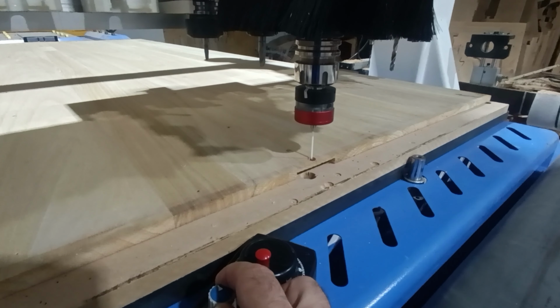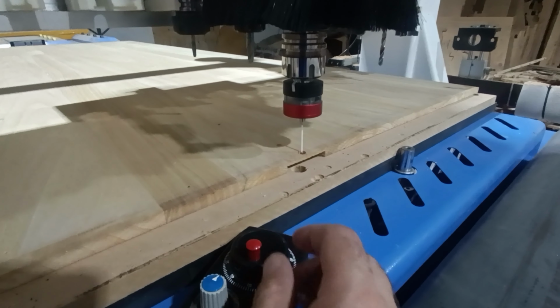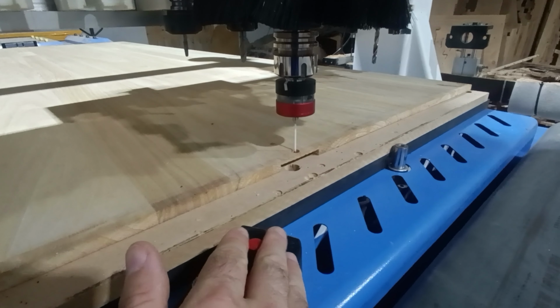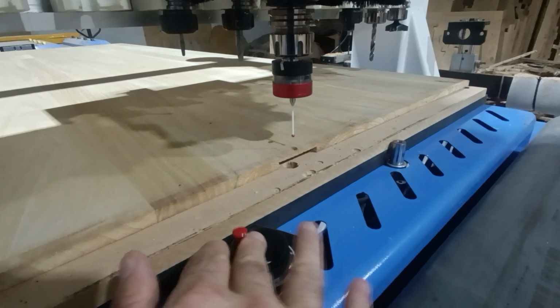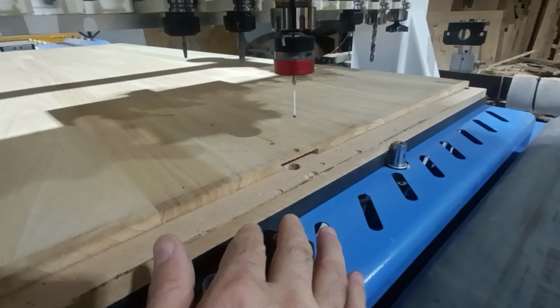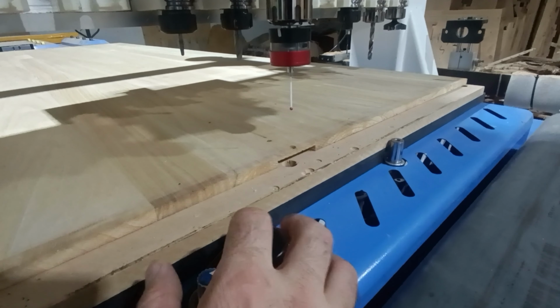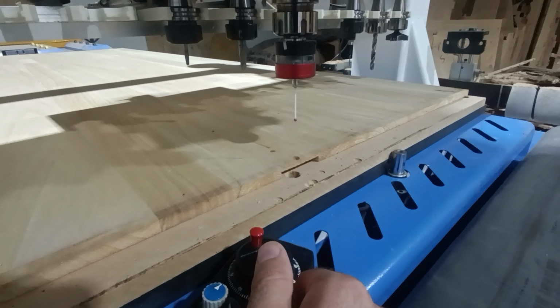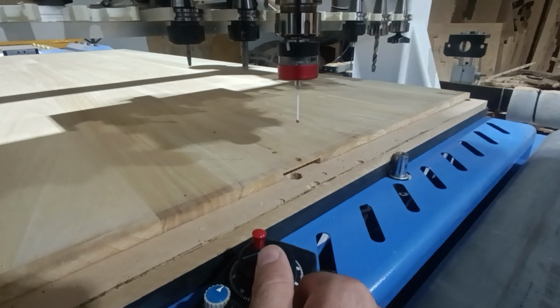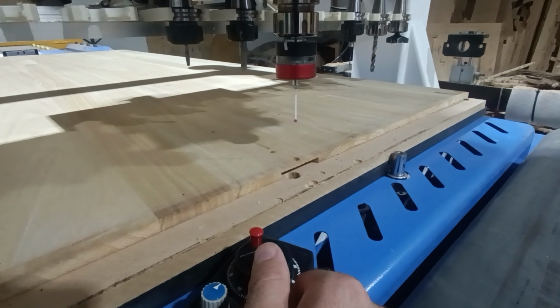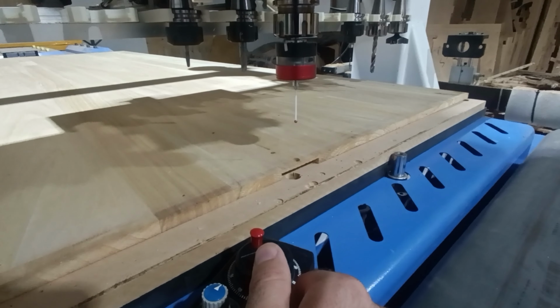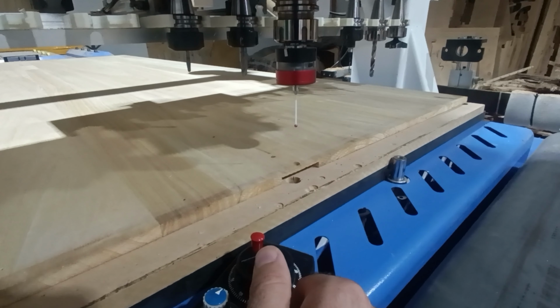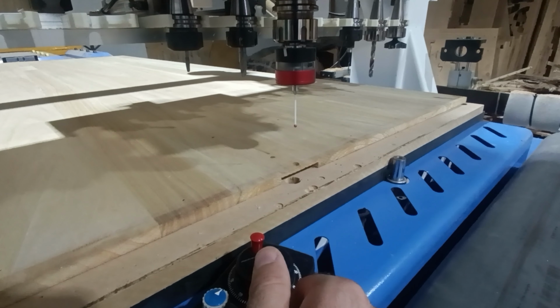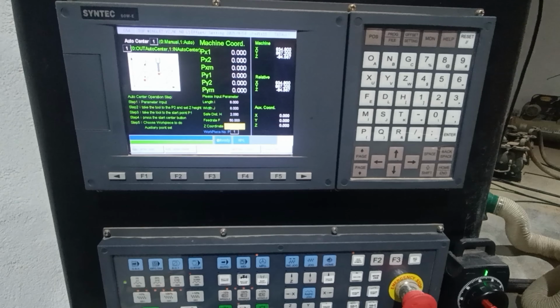When the Z height is set, we can place the ball higher to have a safe distance. This can also be used for outer objects. While measuring, it will go down to the measuring height, but in between the measurements it will go up. This can also avoid collisions.